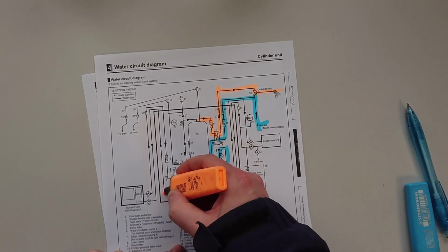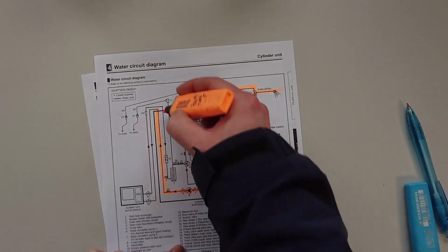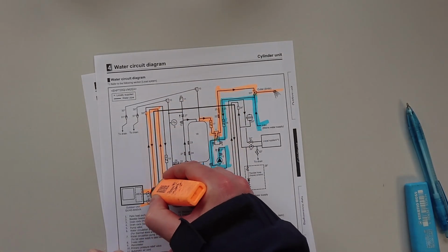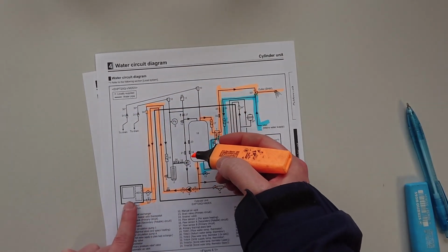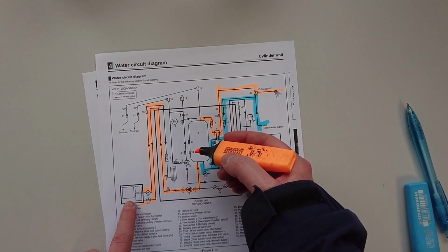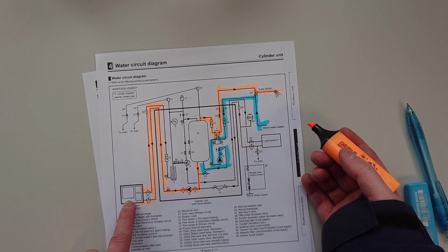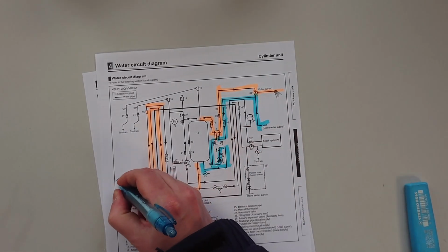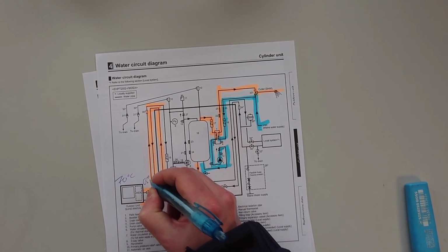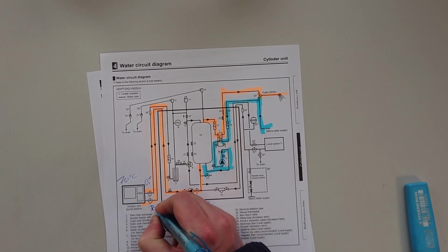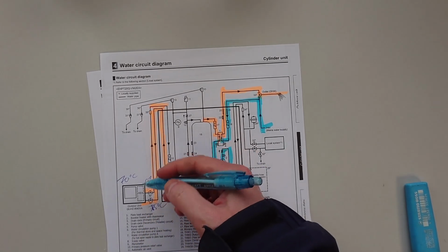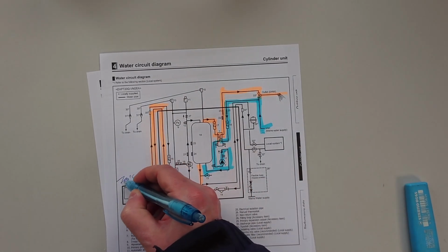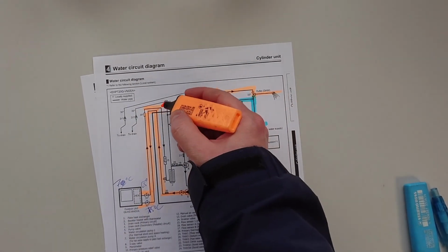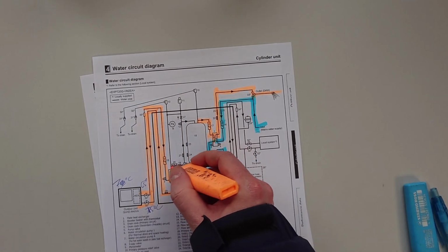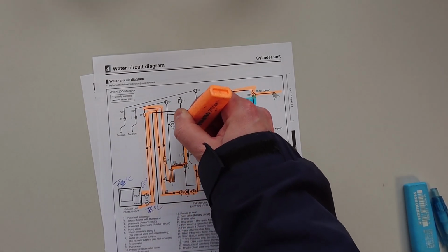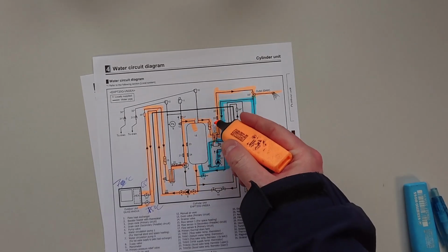Well, we come this way again, we go through this pump that's now pumping the water around to get it into the heat pump. And it goes back out of the heat pump, and I think that's 7 outside temperature again, 15 in, which is about mains water in the UK, and I think it's 65 out, is it? Maybe, can't quite remember. 15 degrees C water in, 65 out, 50 degrees, or 50K lift, and 7 degrees C air on. And then you come back down here, through the heater, through here, and it hits the three-way valve, and it goes, oh, turn left this time, mate. It comes up there, and then goes back into the top of your cylinder.